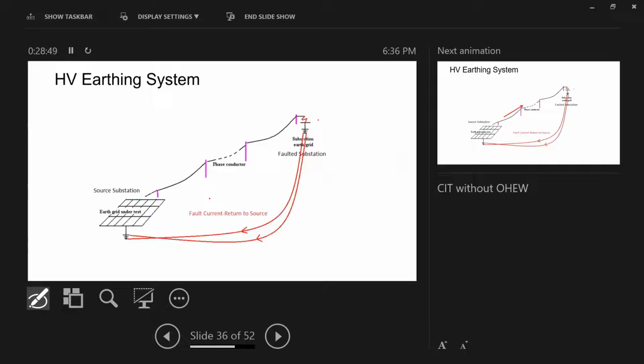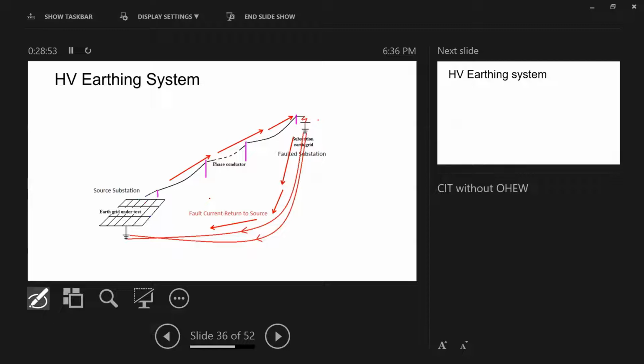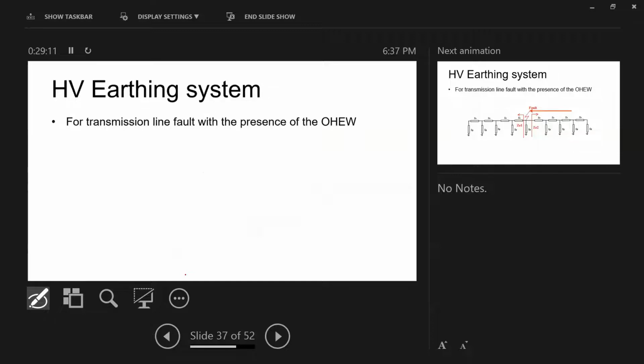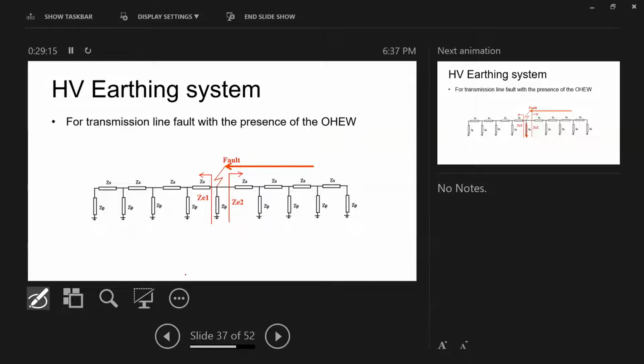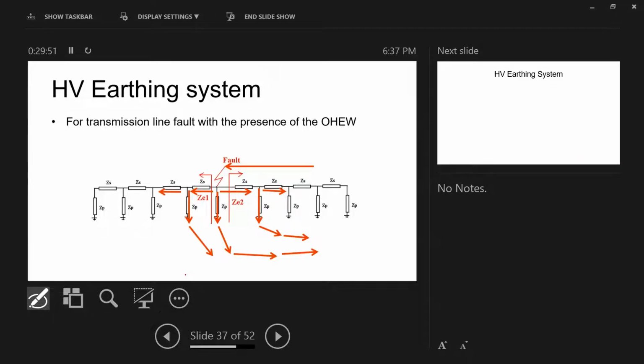If I have a substation without overhead earth wire, look what's going to happen. All the current will go back through the ground. So for a substation without an overhead earth wire, you must have a strong and proper design for your earthing system, because it will be on its own. If I have a transmission line and I have one fault at one pole, I have one wire drop down, part of it will go down into the ground, part of it will go back through the overhead earth wire. Imagine you live next to a pole. Under any fault, this pole is going to take current into the ground. That's why every pole must have a design, must have an earthing system. Every single transmission pole, to make sure that under fault condition, you will have a very low earth potential rise.